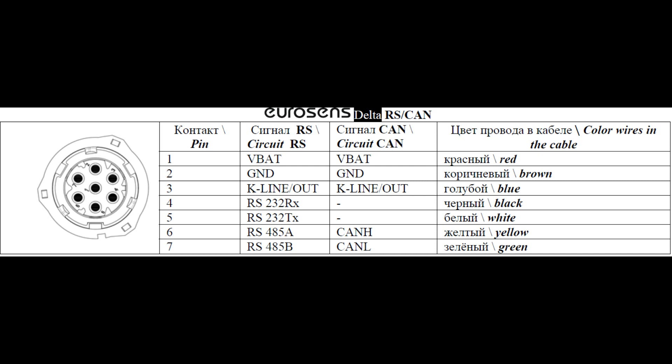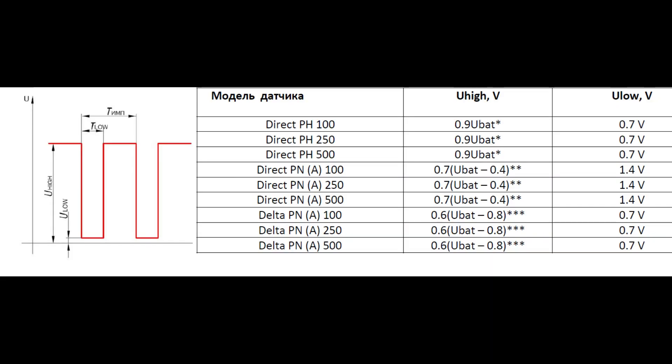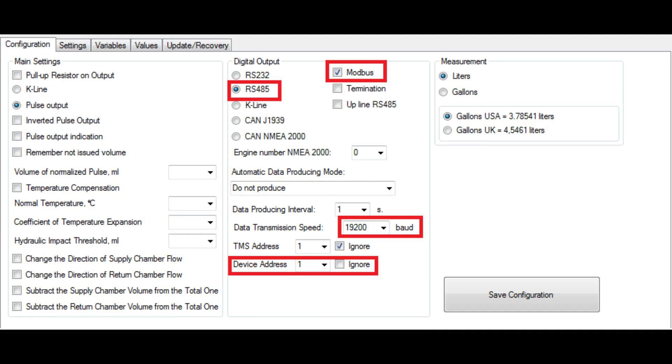Eurosens fuel meters have several possible interfaces. Pulse output, the simplest one, but you will need to count pulses by your data logging device and transform them into fuel data. More advanced are serial RS-485 and RS-232 interfaces, as well as CAN bus.